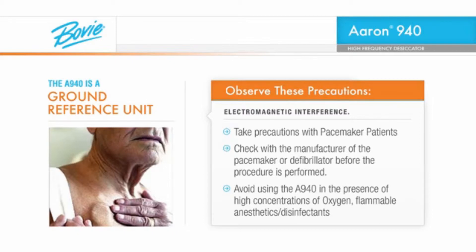Avoid using the Aaron 940 or any other electrosurgical device in the presence of high concentrations of oxygen, flammable anesthetics, flammable disinfectants such as alcohol preps, or any other combustible materials.